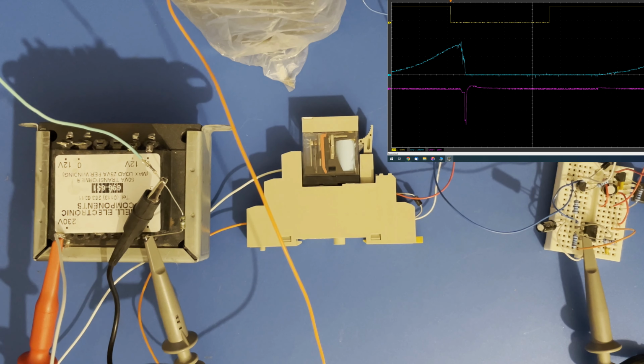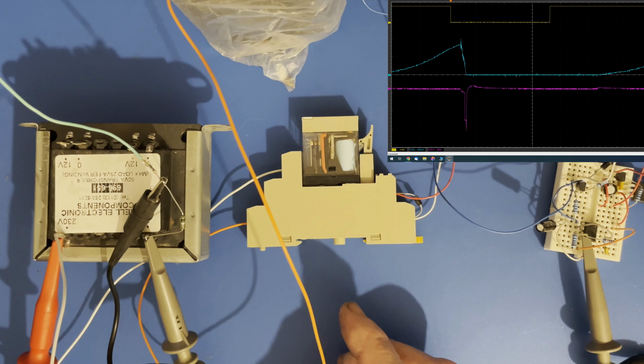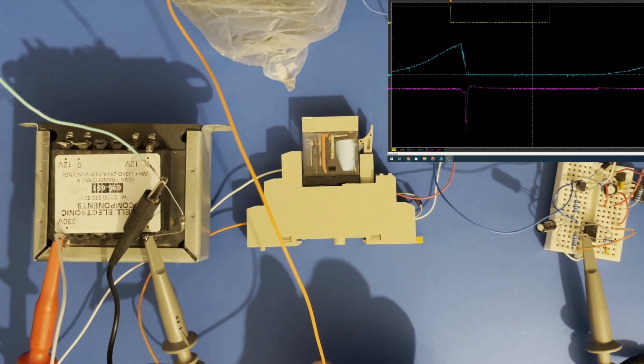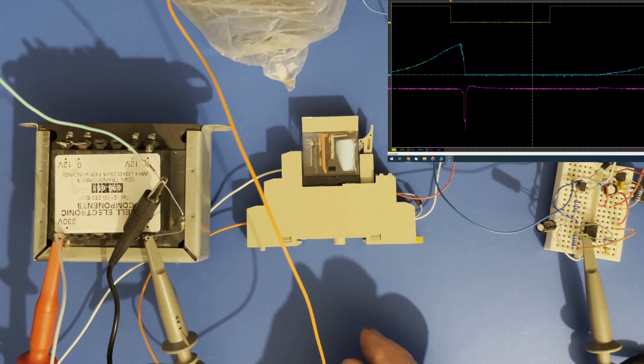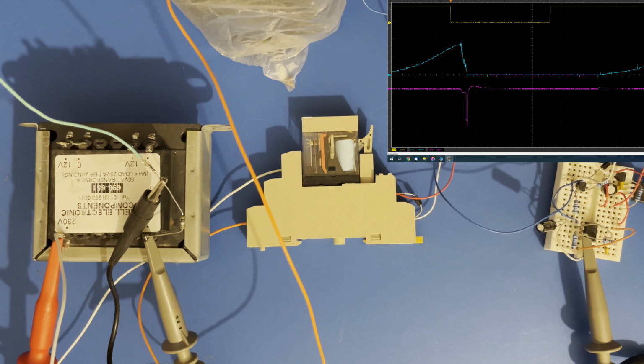And the only thing limiting it to that plateau is the arc on the relay contacts, because they start to arc as soon as they open. And as long as the arc maintains, that limits the voltage to some extent. And there's a little tiny spike as it loses energy and stops arcing.